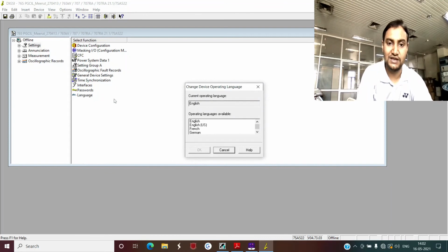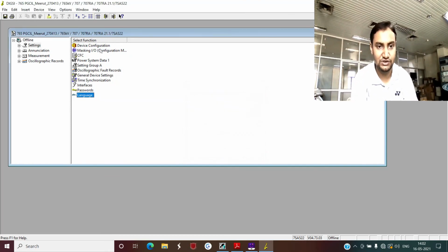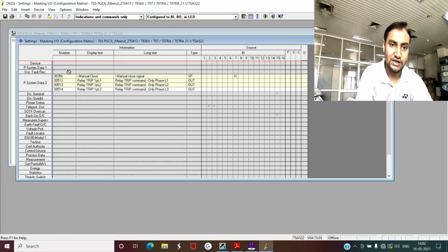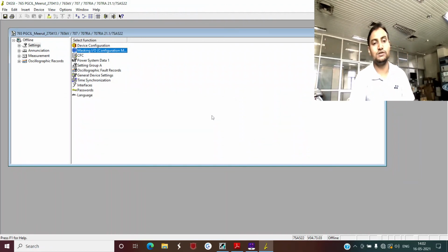Then language is again important, but you can select either English or English US. English US is the general English. If you select normal, then you will have everything in your setting as you see over here, but we will discuss it in later stages. Since we have selected English, and that means English UK, you will have plain English like manual, close, relay, trip, like this. But if you select English US, then in the relay you will see the settings not as distance protection but as 21 protection or 85 or 68, because in English US they will show your settings in case of IEC numbering or ANSI code numbering only.